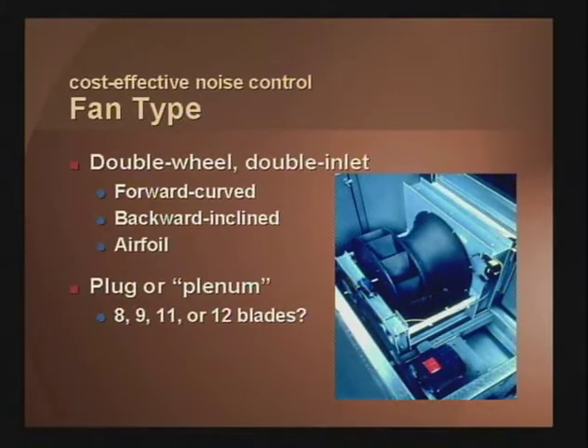Another fan type often selected is plenum fans, sometimes called plug fans. Key thing here is to make sure that you provide the proper spacing around the fan so it treats the air gently as it goes through the fan. Also, take a close look at your blade count on the fan. You want static lift off these fans, not velocity lift. So the more blades you have, the more gently the fan will treat the air. 11 or 12 blades are recommended for acoustically sensitive applications.